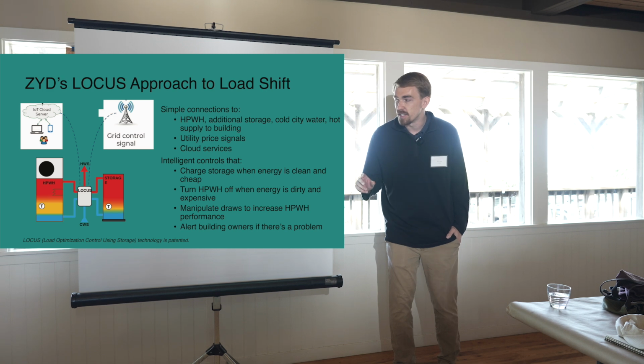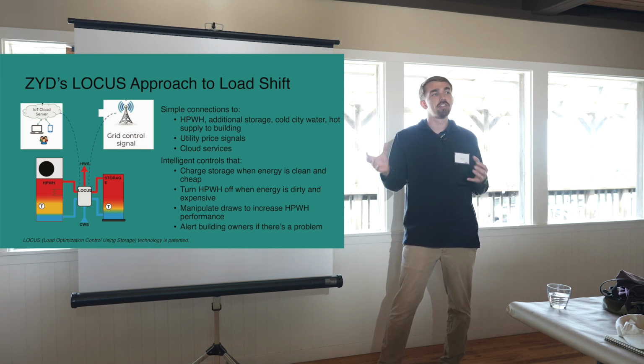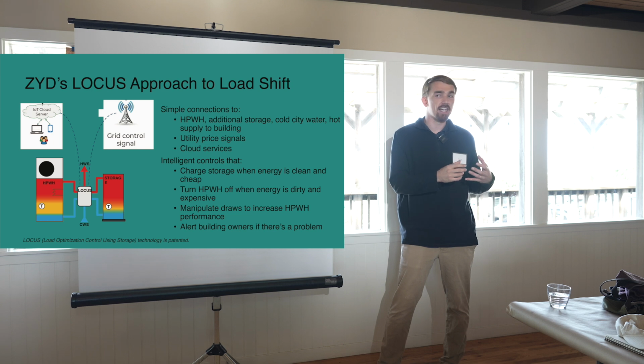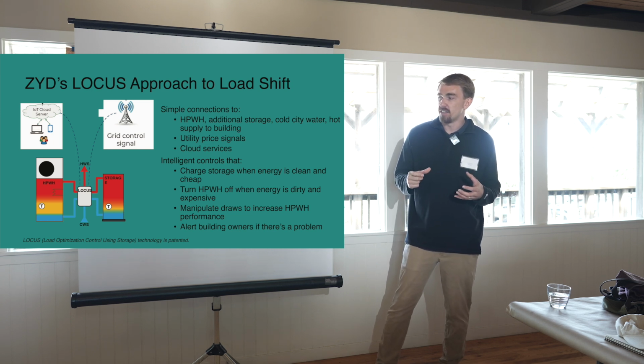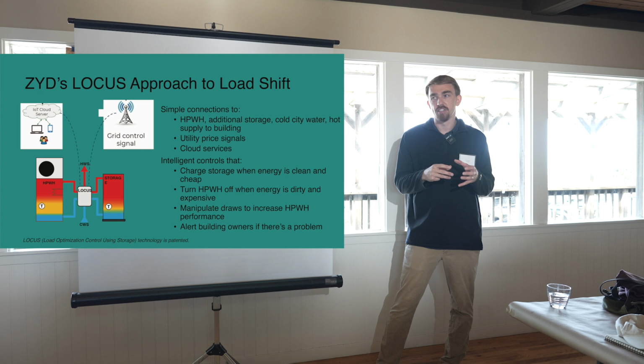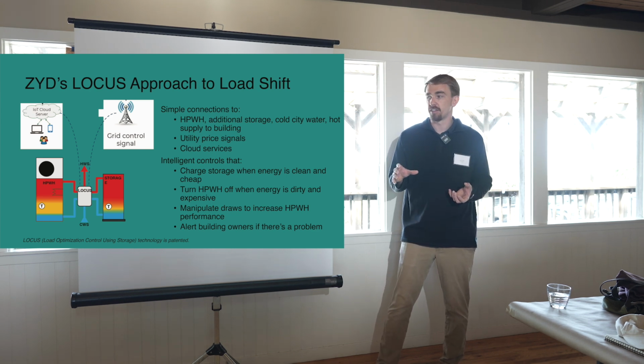So the heat pump is only connected to this locus controller, and the additional storage is only connected to the controller, and that's how the installers are going to be able to install this simply, while the really intelligent locus logic will determine when it will make the most sense to draw from that heat pump and charge the additional storage to handle the load.